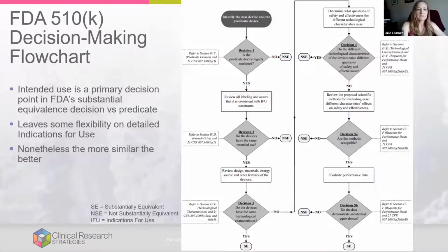So the FDA does provide this decision-making flowchart, and I know that it's small, but you can really just Google FDA 510K decision-making flowchart and find it for yourself. But I wanted to bring it up because it really leads you through what the FDA considers whenever you are considering whether or not a predicate is going to be classified as substantially equivalent or not substantially equivalent. So it's good to look at this ahead of time when you're choosing your predicate. So you start by identifying your new device and the predicate device.